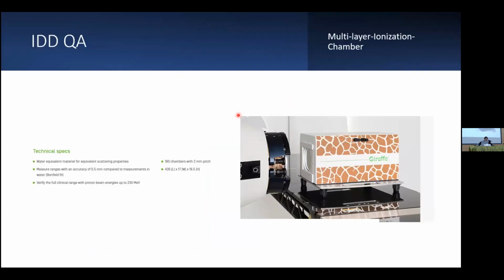Okay. Let's move on a little bit to some different measurements. We talked about the water phantom and doing that absolute calibration. It's also important, on a regular basis, and you have to determine for yourself how often regular means, to measure these integrated depth doses. Something could happen to the machine over time. The other thing is also anytime the vendor has to come in and fix something, you have to check these things. And this is one just out of experience.